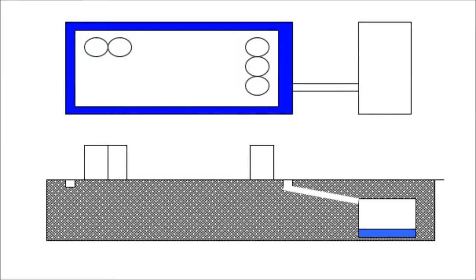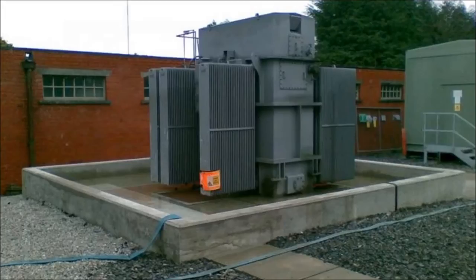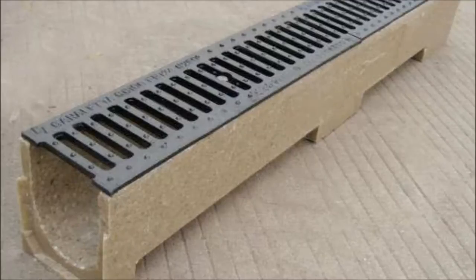If you do not have a large enough floor area for the bund, you may need to consider remote containment. Remote containment is simply a large sump or bund located at a more convenient place, with a pipe leading from the bund to the remote containment. Where there is remote containment, the tanks will often have just a low wall around the perimeter. For drum storage areas, there may be a channel instead of a low wall, which then leads to a remote sump.